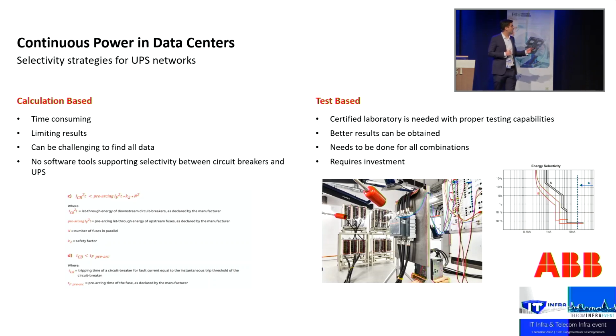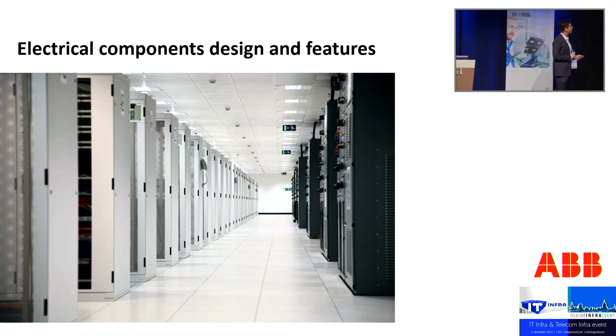So as ABB, we are actually, together with our breakers and our UPSs, we did this calculation for you. So we provide very simple currently tables, so not yet software tools, where you can see which breaker to select upstream and downstream based on the UPS you selected. As sometimes this is even challenging, we also are doing tests in our testing facilities to ensure that there is a proper coordination between the downstream and upstream breakers, so you can even select higher breakers downstream, so you have less constraints when designing a data center. So this would be the first part of the presentation where we share the selectivity.